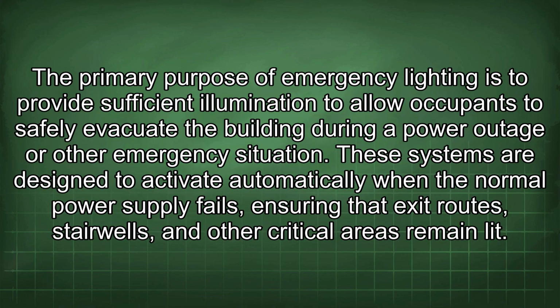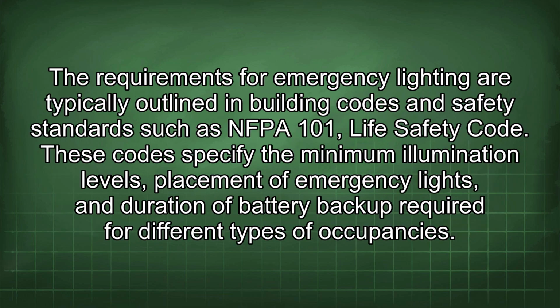The primary purpose of emergency lighting is to provide sufficient illumination to allow occupants to safely evacuate the building during a power outage or other emergency situation. These systems are designed to activate automatically when the normal power supply fails, ensuring that exit routes, stairwells, and other critical areas remain lit. The requirements for emergency lighting are typically outlined in building codes and safety standards such as NFPA 101, Life Safety Code.